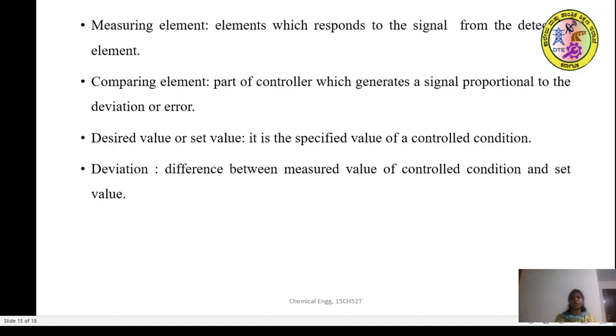So what is the measuring element? The measuring element is the element which responds to the signal from the detecting element. The comparing element is a part of the controller which generates a signal proportional to the deviation or the error. So what is the desired value, or the set point value? It is the specified value of the controlled condition. Deviation is an error, the difference between the measured value of the controlled condition and the set value.